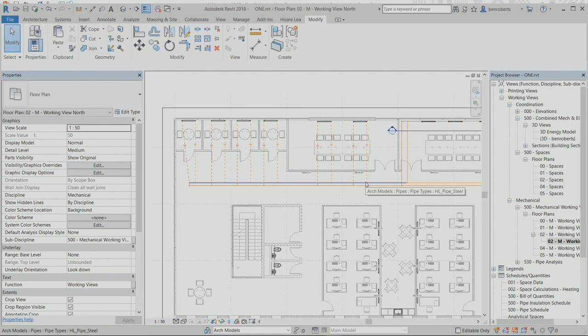So to get away from these issues, analytical pipe connectors. We can select a bunch of radiators here, click Analytical Connections - this is a new feature in 2018 - and then I click on the flow pipe, and it connects all the flow connectors, and the return pipe, and it connects all the return connectors. This hasn't physically drawn any pipe, it's just a logical connection between the two, okay?